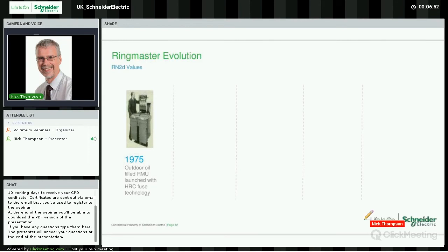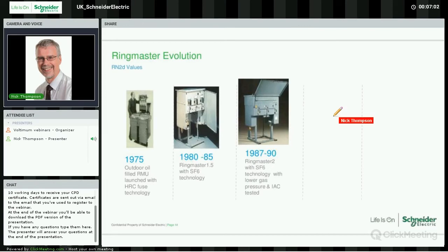We've got here in the 70s or earlier than that, we used oil, using fuses to protect the transformer. Moving on from there, we had then SF6 gas with two units, firstly with Ringmaster 1.5, and the number there, 1.5, is referring to the current rating of the circuit breaker. As time and technology moved on, Ringmaster 2 was brought out.